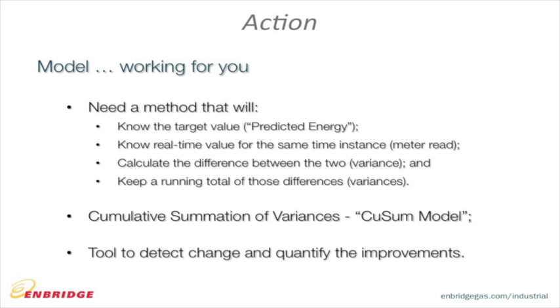So we need a model that will tell us what the target value is, what's predicted energy. We need something that will tell us what's the current reading, what's your meter reading. We need something that's going to calculate the variance between the two, the difference between predicted and instantaneous. And we need something that's going to keep a running total of those.